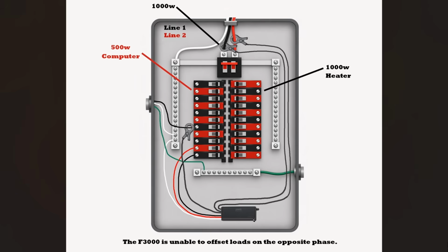The Anker smart meter will see that, and you can view it in the app, but there's nothing it can do about it unless you have a second F3000 installed on line 2. I wanted to demonstrate that line 1 and line 2, or phase 1 and phase 2, are completely separate. With a 120 volt device, you can only backfeed to one side, so you'd need two F3000s, or you have to plan out which side you want the F3000 connected to.